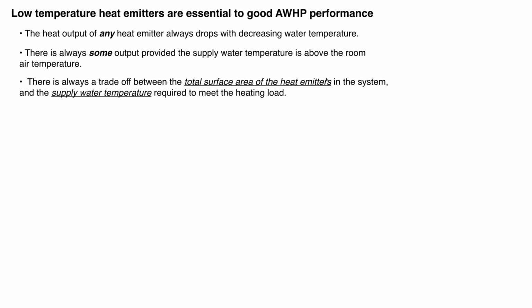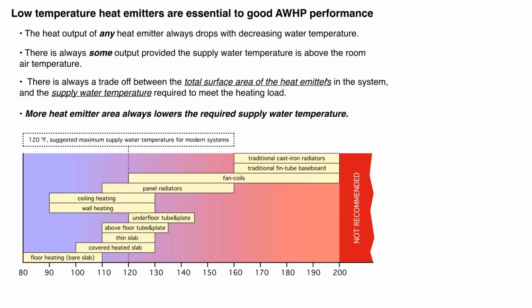And then the fundamental trade-off. The more surface area your distribution system has, the lower the water temperature can be. And you can think of that sort of like a seesaw. On one side, you've got the surface area of all the heat emitters. On the other side, you've got supply water temperature. When one side goes up, the other side goes down. So fundamentally, what we're trying to do is create distribution systems that have a lot of surface area, okay?